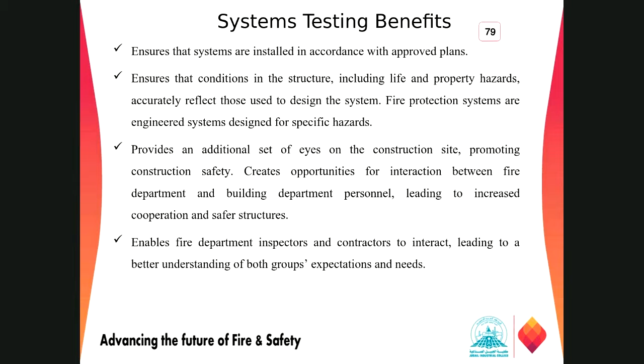And then we have the maintenance and retest, right? Now we are normally going to NFPA 25, which has given the maintenance requirement, how you are going to maintain your fire protection system, what is the time interval, what is the maximum duration between maintenance of these particular items, what is the time for one system. This all will be followed by the code under which the system is installed, the jurisdiction, the one who installed those fire protection systems, right?